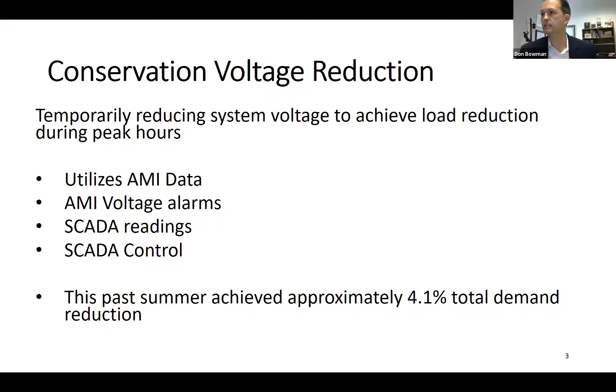This past summer we achieved about 4.1% total demand reduction on our system, which can get up to 8 megawatts of reduction during peak just from reducing voltage. This requires nothing active from the consumer—in fact, no one knows we're doing it. We've done this for 7 years with zero residential complaints, yet we see significant reduction when it occurs.